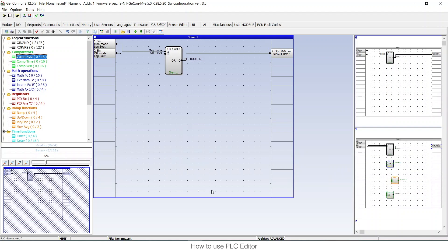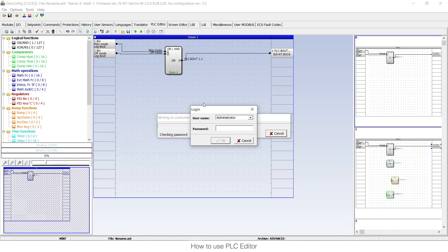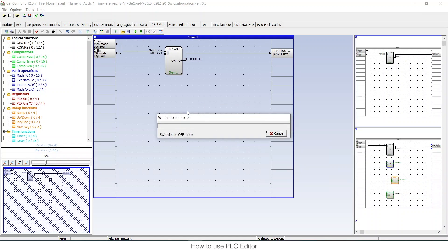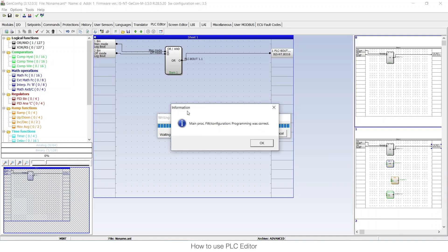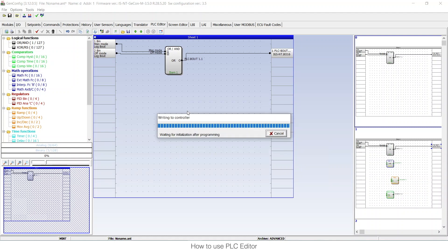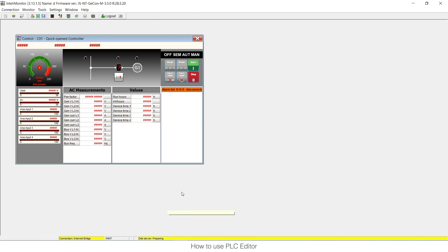I'm going to delete the extra block. The PLC should activate binary output 16 when in manual or off mode. I'll write the configuration to the controller — as you know, every time you use GenConfig you need to write the configuration. It will ask for the admin password, which by default is zero or one in Comap. Now it will be programmed. We're waiting for initialization — it takes some time to restart the controller — and then we'll go to IntelliMonitor to check what we did.